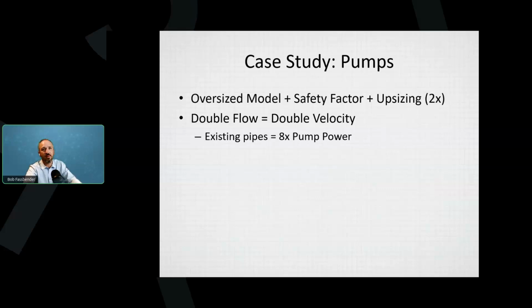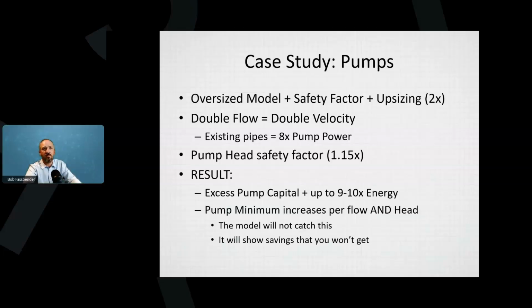This is if, and I see this happen, it shouldn't happen, but it does. Add a pump head safety factor, and the result is you spend a lot more on your pump, and it uses 9 to 10 times more energy than it should. The real bad part is that this may not be fixable. The pump minimum flow cannot be fixed by a variable speed drive, and the pump head causes an issue. The model will not catch that. And the model will actually still show savings, and you won't get that savings.